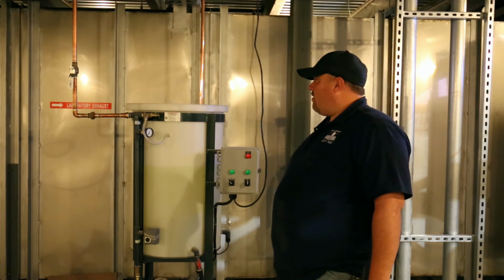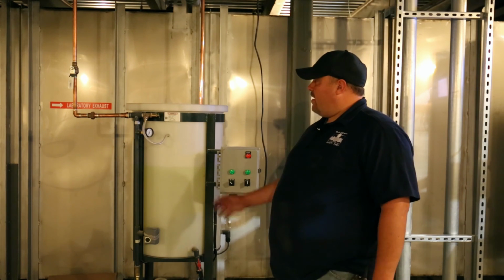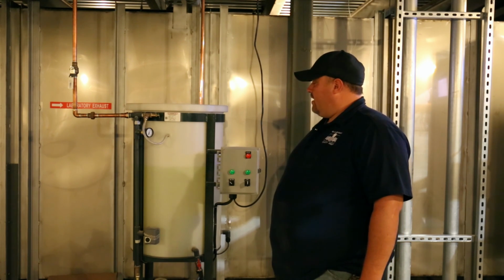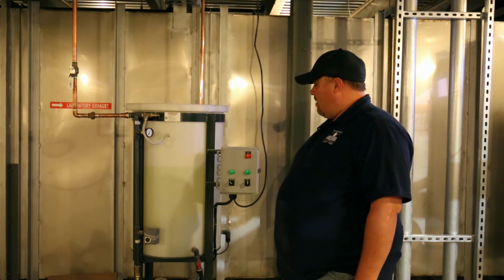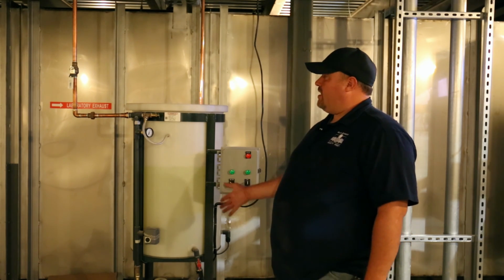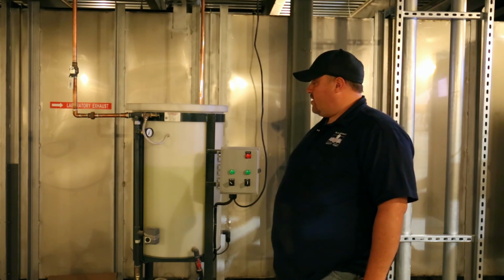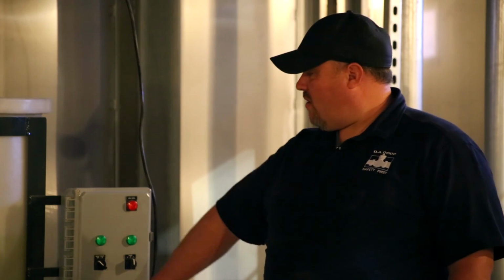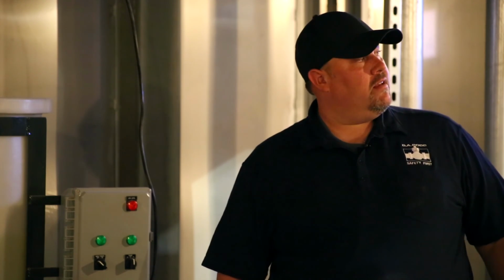Here we have our glycol feeder. It is currently operating at 36 PSI. It's a 55-gallon drum with its own positive displacement pump to feed whatever desired pressure automatically to the system for makeup glycol feeds. In the event that we would have a leak, this would turn on and automatically feed to the system, and or purge the automatic air and dirt separator.